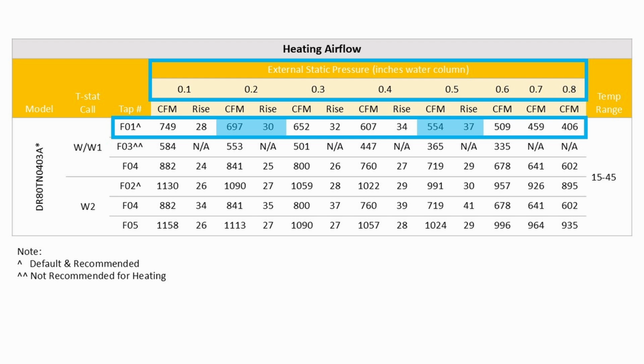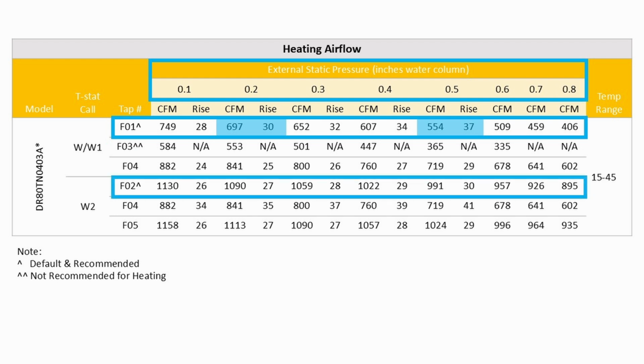On a call for W2 at F02 fan speed, CFM of air is 1090 with a temperature rise of 27 degrees. At 0.5 inches of static pressure, CFM is reduced to 991, temperature rise is increased to 30 degrees. Nominal temperature range is 15 to 45 degrees Fahrenheit.